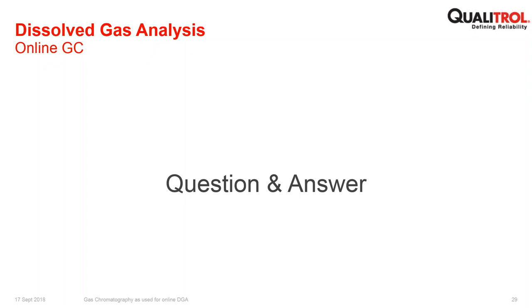Okay. There's a few questions that are similar, so I'm going to paraphrase, and if it doesn't address what folks are looking for, let us know. Is this more applicable to the monitoring itself? Is it more applicable to a new build or something that we're retrofitting? It's perfectly suited to either. The monitor can be installed on the transformer if it's part of, let's say, a new build, and for convenience, the OEM would want to mount all monitors or all systems on the main tank. So it's suited to tank mounting. It's also suited to retrofit, I guess, if possible on the tank mount, but also on a pedestal mount, which we have as an option.